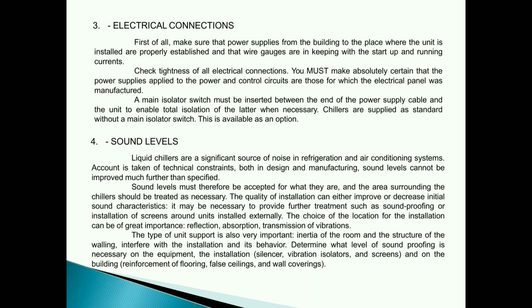1.3 Electrical connections. First of all, make sure that power supplies from the building to the place where the unit is installed are properly established and that wire gauges are in keeping with the start-up and running currents. Check tightness of all electrical connections. You must make absolutely certain that the power supplies applied to the power and control circuits are those for which the electrical panel was manufactured.